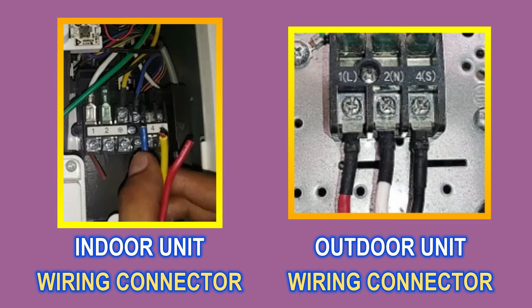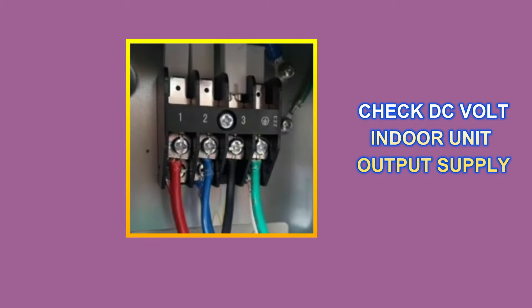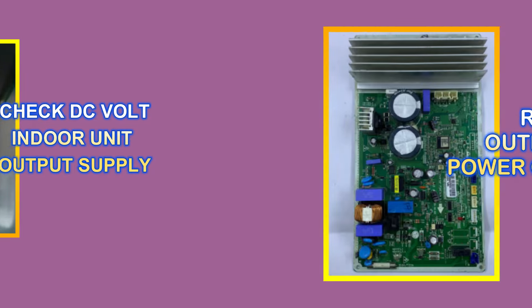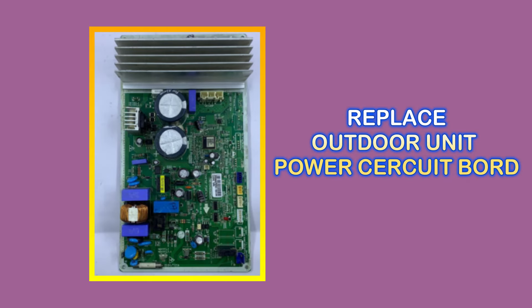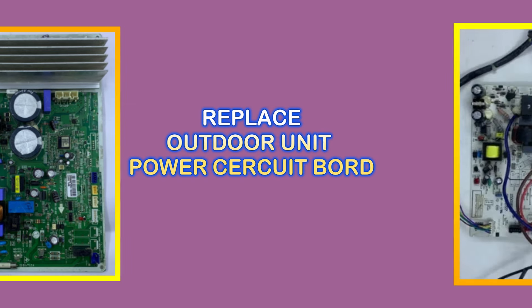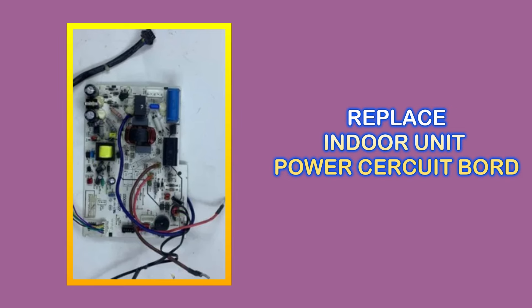If the same color code wire is installed and the error is still coming, then another reason could be a voltage issue. Turn on the indoor unit and open the wiring cover of the outdoor unit. Now check the DC voltage at the output supply of the indoor unit. If the indoor unit is providing DC output supply and you are still getting this error, then you will have to replace the PCB of the outdoor unit. If the indoor unit is not providing output supply, then you have to replace the power circuit board of the indoor unit.